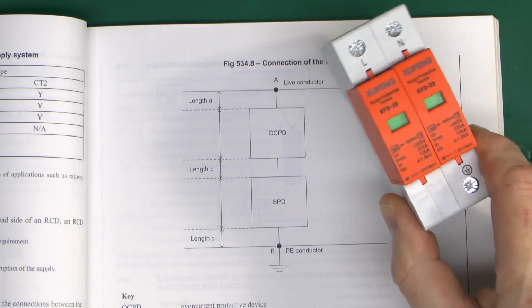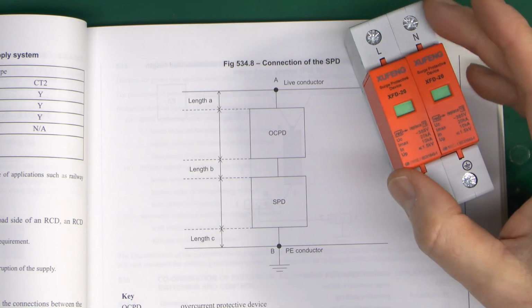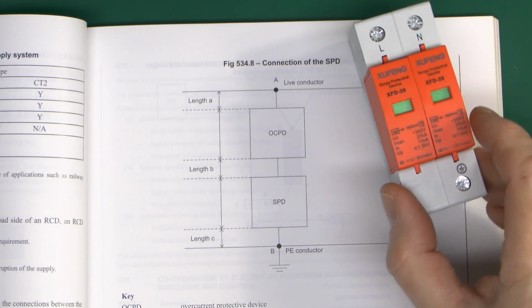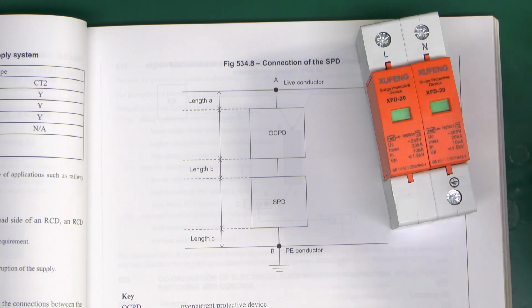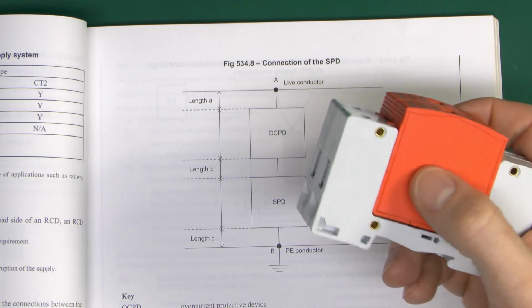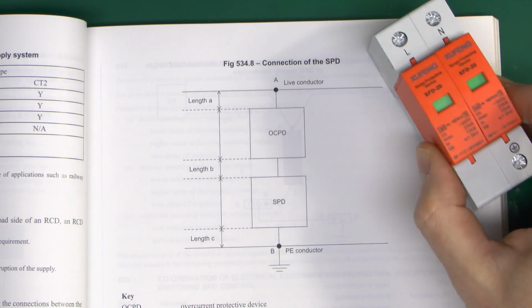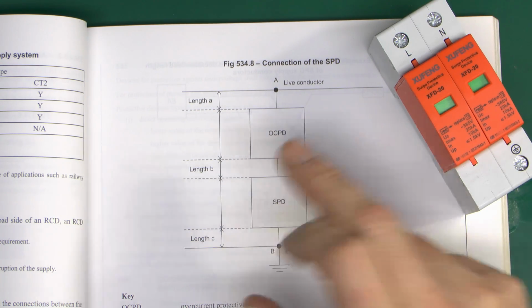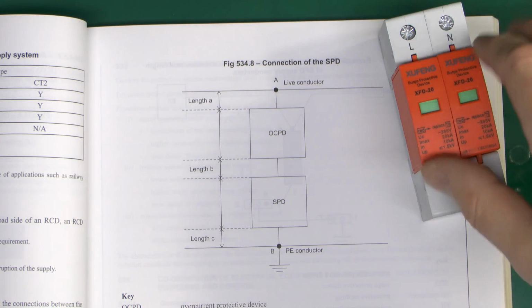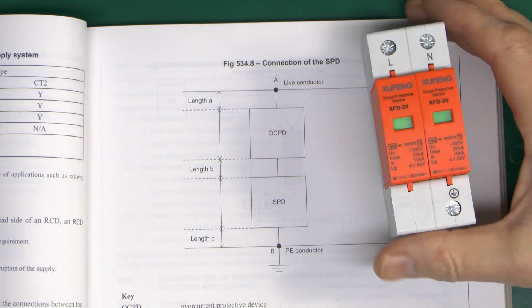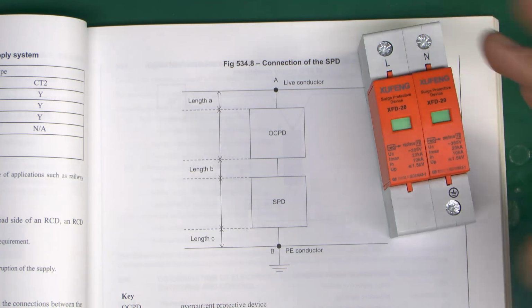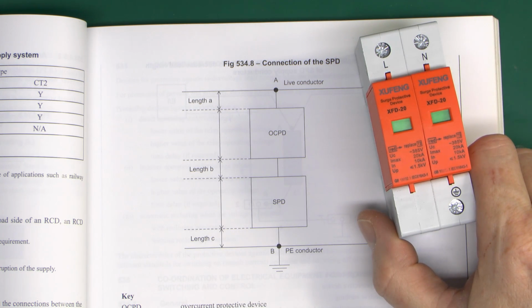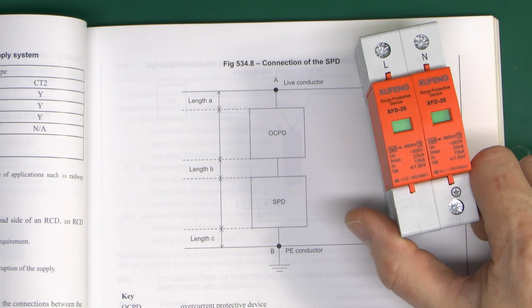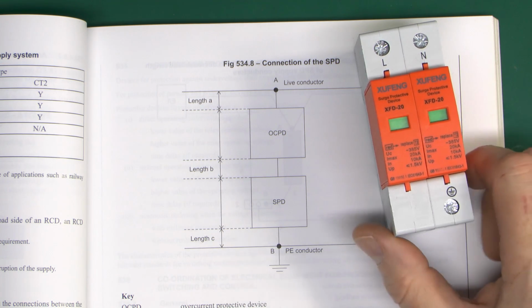Now there is a difference in some of these. These particular ones require an external overcurrent protective device, and that's quite often provided with a circuit breaker just next to that onto the line conductor. Some of these from some manufacturers do actually have a fuse built inside, and that's basically the overcurrent protective device here. Whether you actually need a separate circuit breaker or not really depends on the manufacturer, so just follow the manufacturer's instructions for that. That will also tell you what size of circuit breaker or whatever to use. Certainly for a smaller domestic installation, 16 or 32 amps is a fairly common choice, but some of them do actually have a fuse built in.